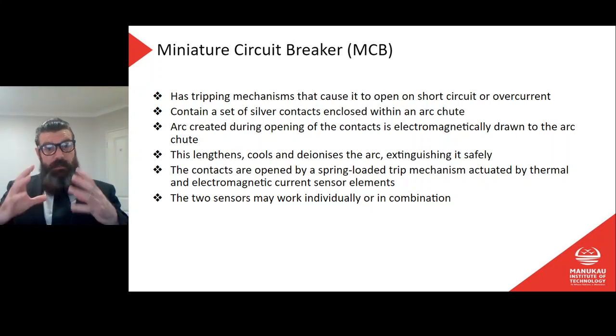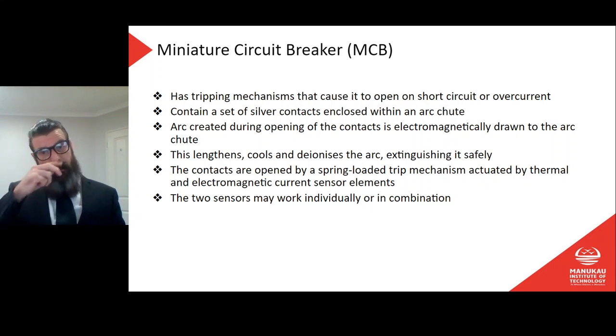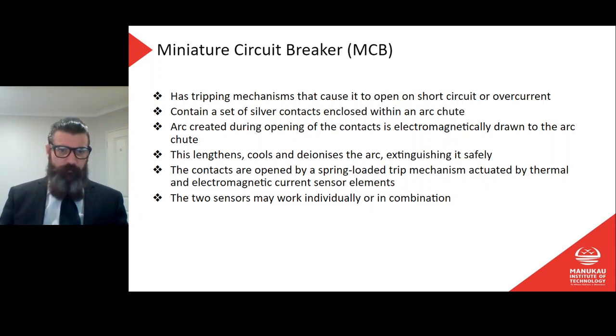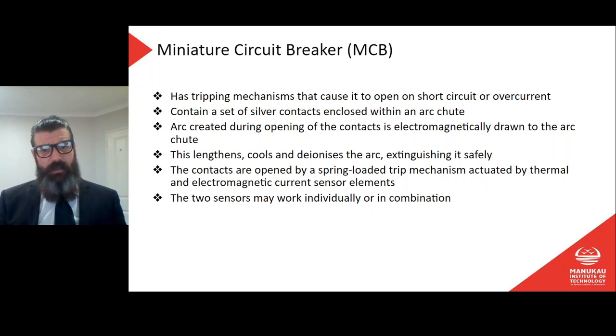An MCB has two types of tripping mechanisms, right? One that opens on a short circuit, one for an overcurrent. It contains a set of silver contacts enclosed within an arc chute. The arc created during opening of the contacts is electromagnetically drawn to the arc chute. This lengthens, cools, and deionizes the arc, extinguishing it safely. The contacts are opened by a spring-loaded trip mechanism actuated by a thermal and electromagnetic current sensor element. The two sensors may work individually or in combination.